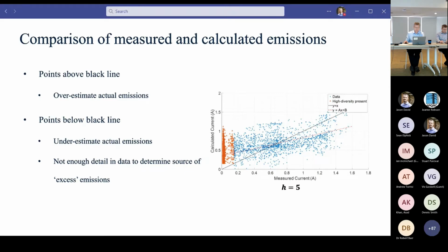That suggests there are harmonic sources present in the network or circuit that aren't captured by the individual generator monitors. Unfortunately, we don't have enough detail in the data to determine the source of this excess, but it's certainly an area for more thought. Also in terms of this graph, we've got a high number of measurements in which the summation of the individual generator emissions exceeds the minimum measurement threshold for the collector cable monitor, but which don't actually exceed that current that flows through the collector cable. Those are the orange points there. And as shown in the previous slide, this accounts for, what was it?